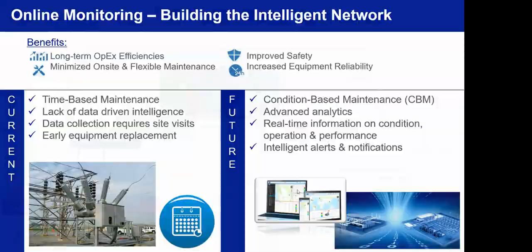We have wind and weather conditions used as input as well. They can encourage us to optimally utilize assets, meaning going beyond limits, for example 25% overload, instead of building new assets. But operational tripping schemes are also important for system integrity, and they can rely on dynamic thermal line rating when thermal limits are the constraint in the network.